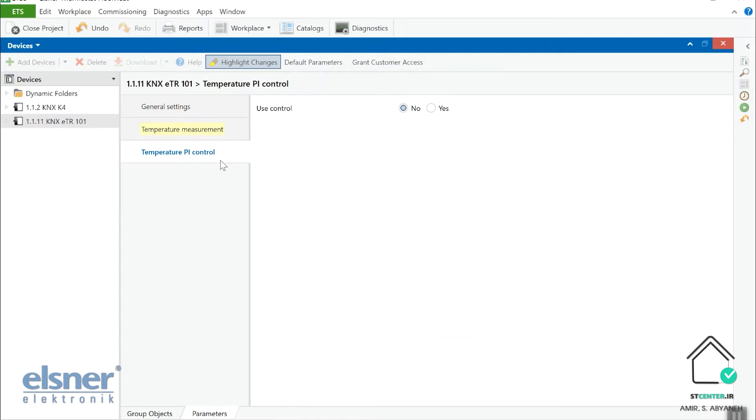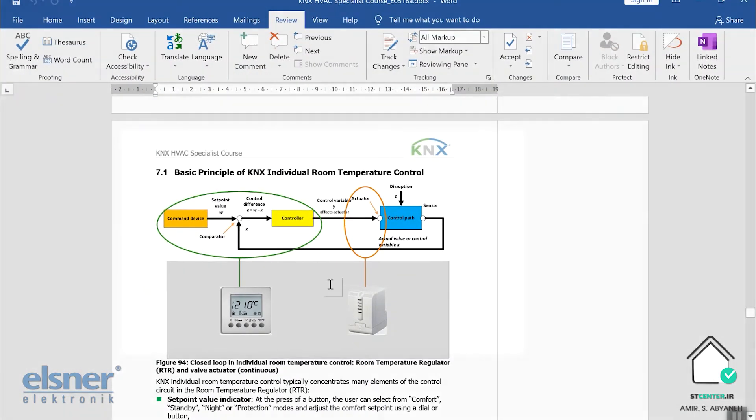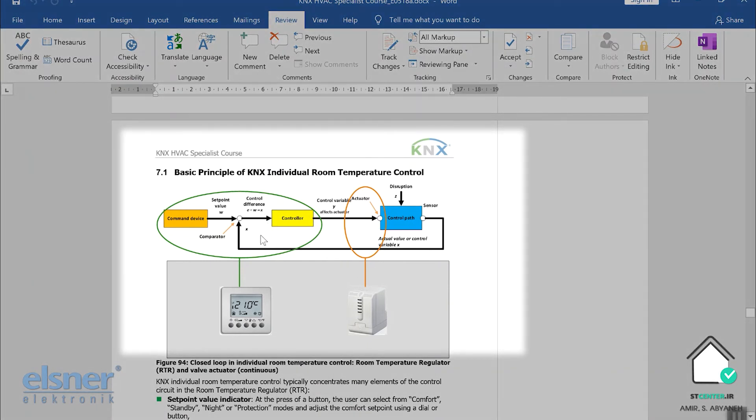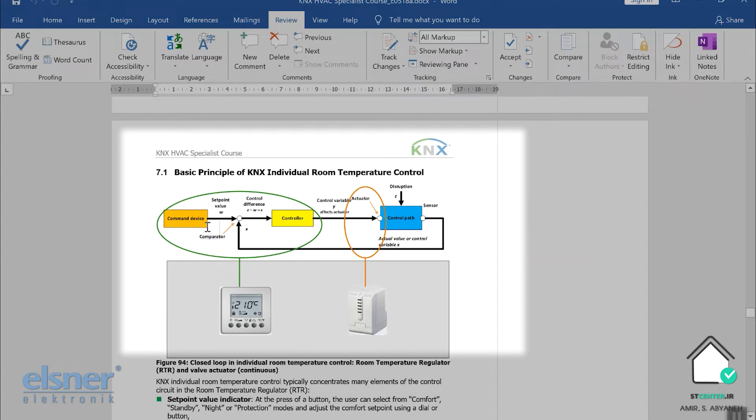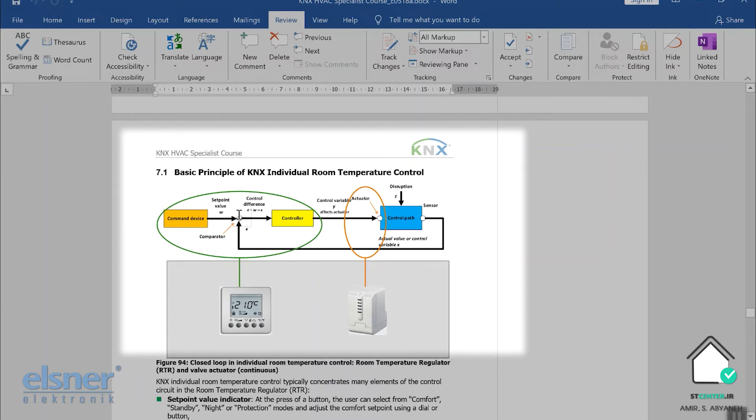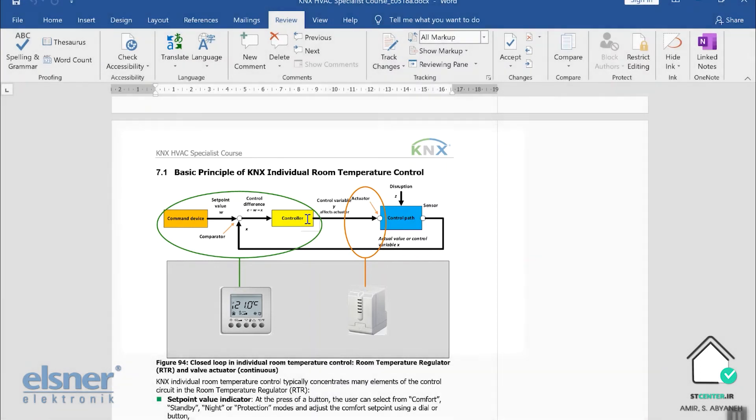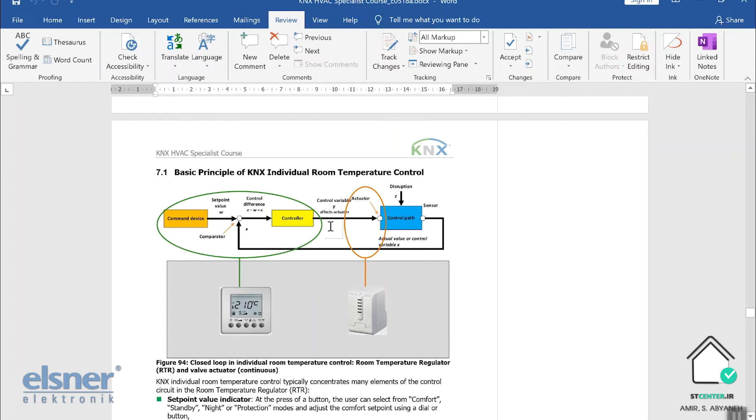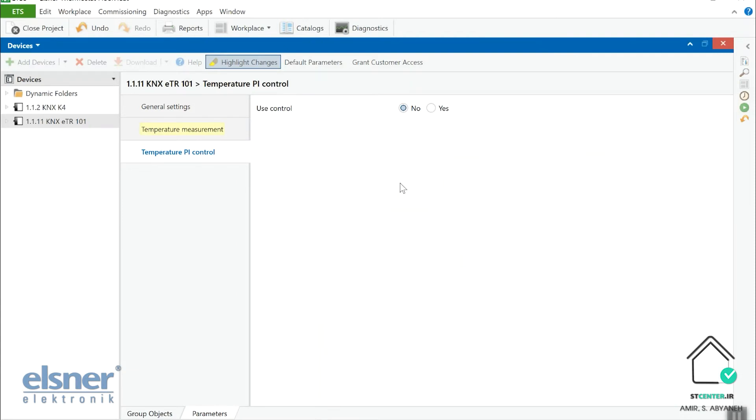In temperature PI control, this is a closed loop control. In mechanics HVAC books, you can see the closed loop controller. The thermostat includes the common device. So we can import or enter the set point that we need in a room. There is a temperature sensor inside of it, so it can detect the temperature of the room. It compares between set point and the read temperature, makes the control error or control difference. This control difference is going to the controller, and the controller in our case is a proportional integral controller. It can receive the control difference or control error and make the control variable or control value. And the output of it is going to the mechanics actuators. So here first of all, we should make the closed loop controller on.